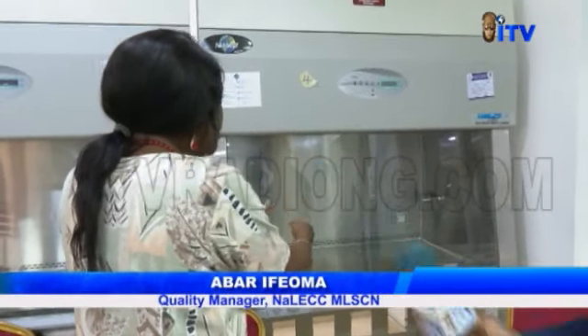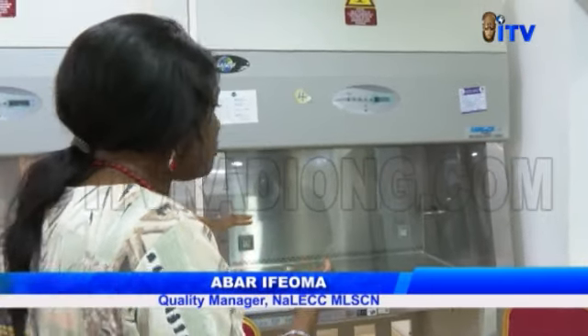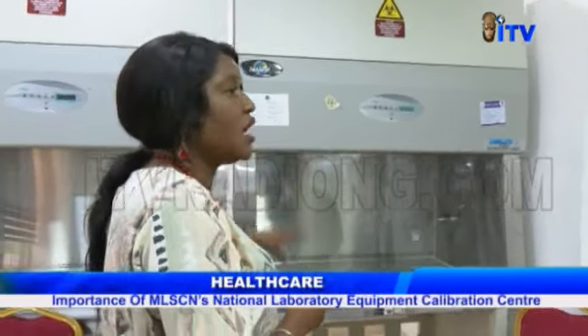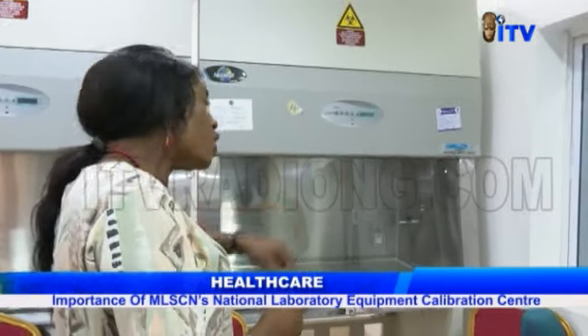We have so many parts inside it that mop up the aerosols coming out from the particular organisms, to make sure they are not exposed to the outside world and do not affect the staff. The importance of the biosafety cabinet is to safeguard the person who is carrying out the test. Maybe you are running a TB test, for instance. The aerosols, you cannot inhale them, and at the same time they cannot escape from the chamber. Instead of escaping, the cabinet traps them inside the chamber.